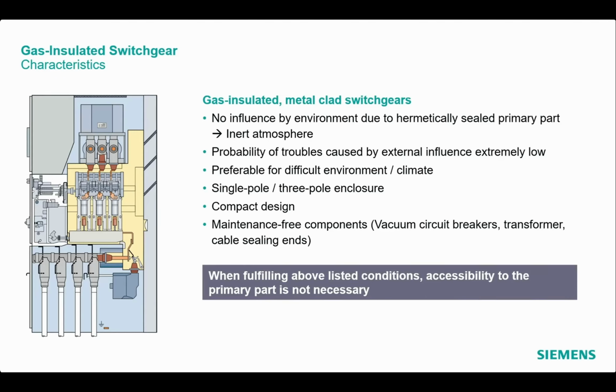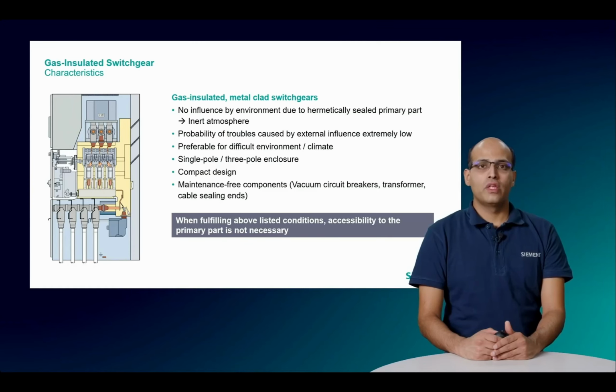Since the primary parts are enclosed inside the gas compartment and hermetically sealed for lifetime, there is no influence from the environmental conditions. The probability of troubles caused by external influence are minimum, thus making them preferable for challenging climatic conditions. The GIS have designs with single pole as well as three-pole enclosure, meaning each pole individually or all three poles are encapsulated together in the gas compartment. The inherent excellent dielectric characteristic of gas helps in compact design of the switchgear. Moreover, GIS provides a maintenance-free design. When fulfilling the above listed condition, accessibility to the primary part is not necessary.